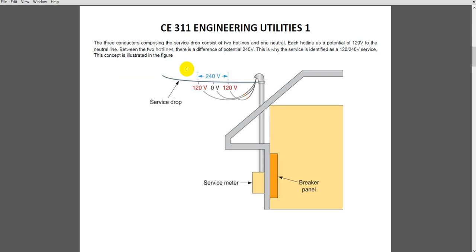So, this system: the three conductors comprising the service drop consist of two hot lines and one neutral. Each line has a potential of 120 volts to the neutral line. Between the two hot lines, there's a different potential of 240 volts. This is why the service is identified as a 120-240 service. This concept is illustrated in the figure. So in some places, three wires enter the service entrance, comprising two 120 volt lines and a neutral at 0 volts. When you combine the two 120s, you have 240 volts.